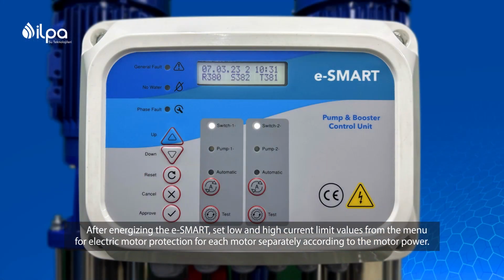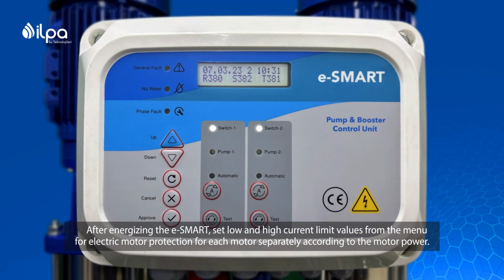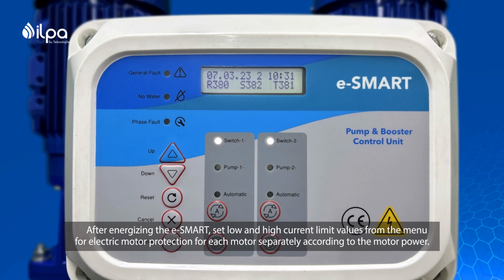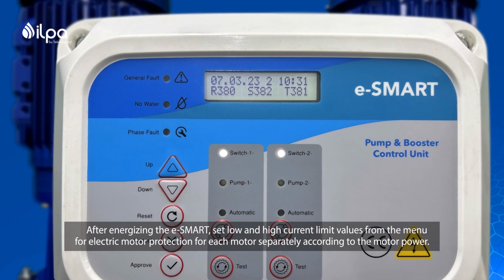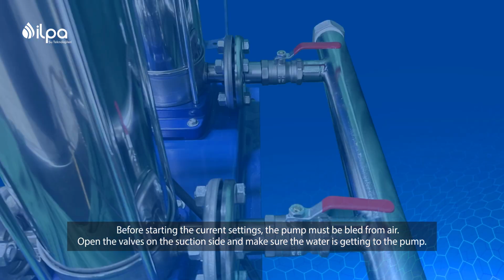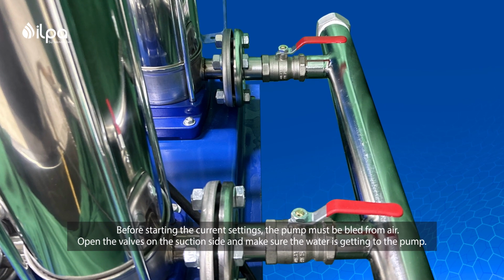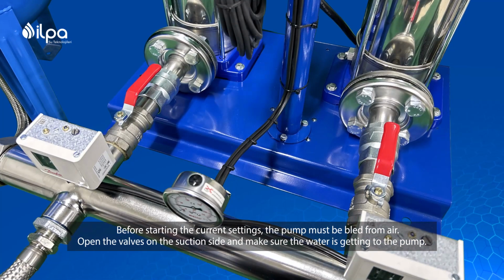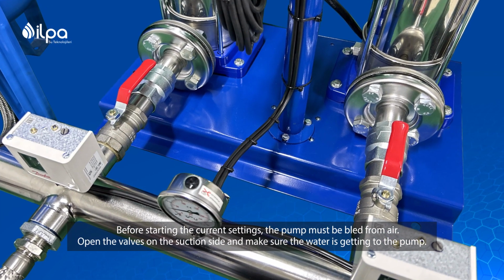After energizing the eSmart, set low and high current limit values from the menu for electric motor protection for each motor separately according to the motor power. Before starting the current settings, the pump must be bled from air. Open the valves on the suction side and make sure the water is getting to the pump. Close the valves in the discharge line.